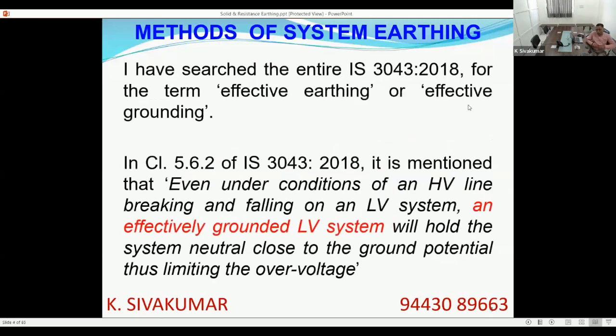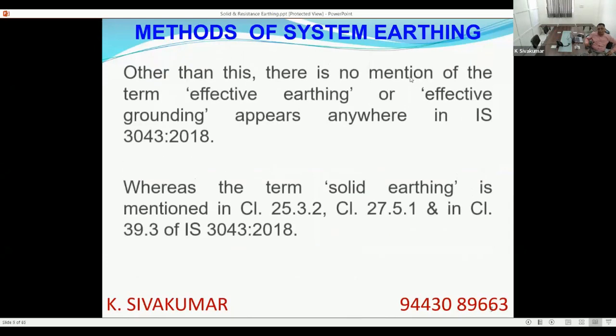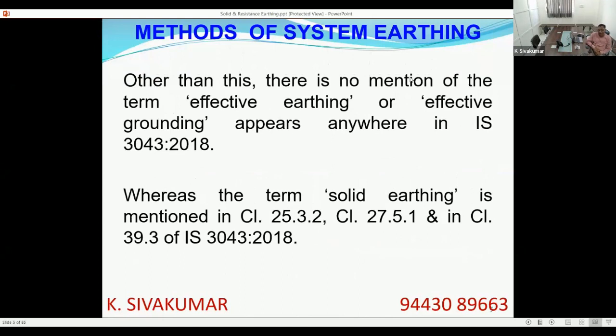So if you look into the Bible of earthing in India, that is IS 3043, and make an effective earthing search, in only one place, clause 5.6.2, does the Indian Standard Code of Practice for Earthing mention an effectively grounded LV system. It mentions what will happen in an effectively grounded system. That's all. But it does not explain what is an effectively earthed system or what is a non-effectively earthed system. There is one passing mention of the term effectively grounded system in IS 3043. Other than this one area, clause 5.6.2, there is no mention of the term effective earthing or effective grounding anywhere else in IS 3043.